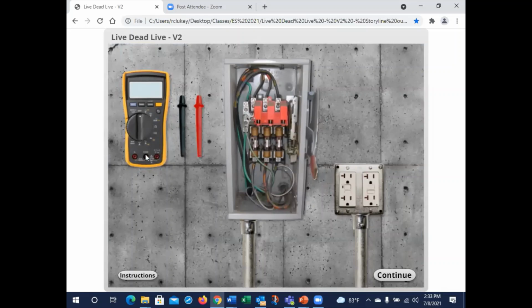I would want to make sure that my meter is adequately rated for the environment that I'm going to be doing this procedure in. For example, if I'm in an industrial or commercial setting and I am indoors, a category 3 meter could be used. That would give me a transient protection if it was 600 volt rated up to 6,000 volt transient. If it was 1,000 volt rated Cat 3, it would give me 8,000 volt transient protection. So I got to make sure I have the right category of meter in my hand. And so then I'm just going to turn my meter on. We can see it's saying 0 now.